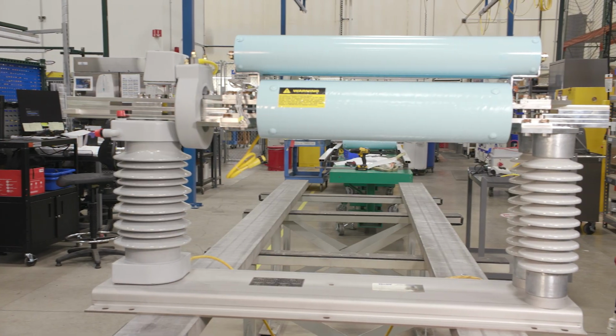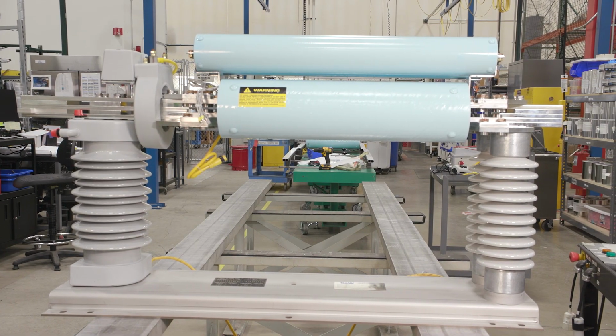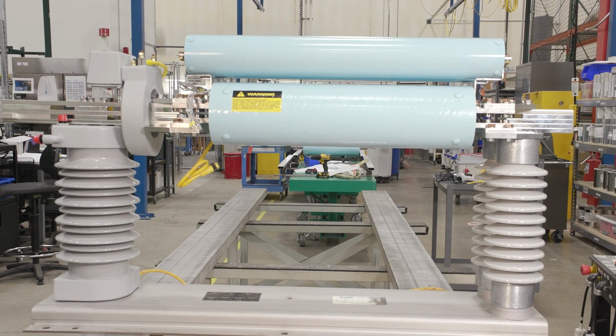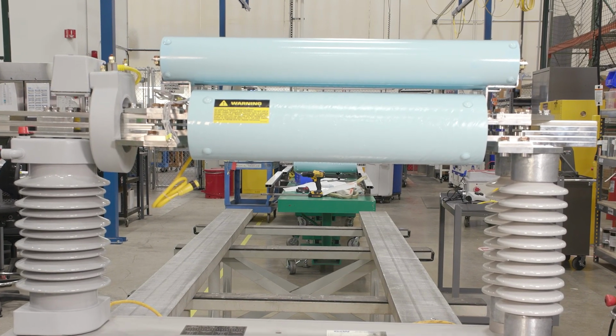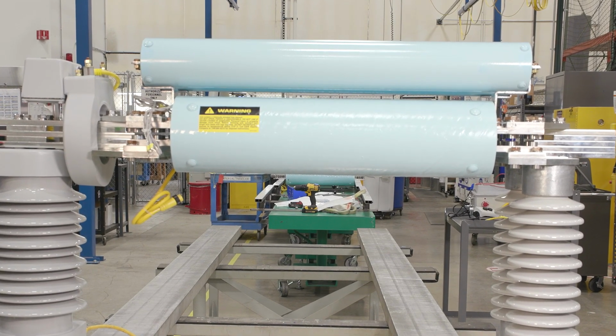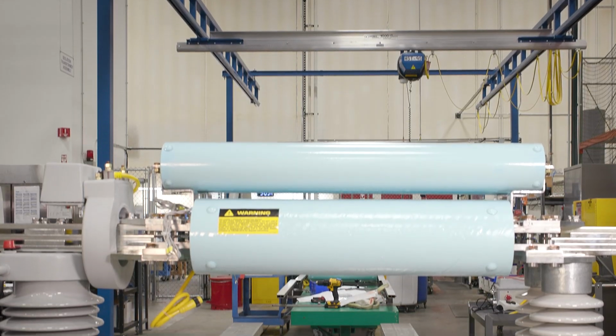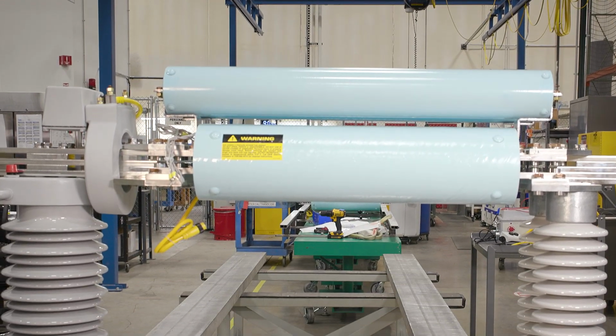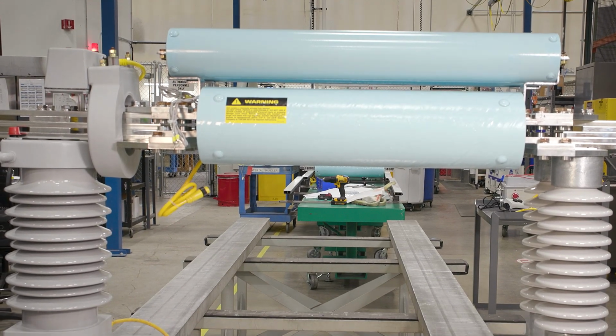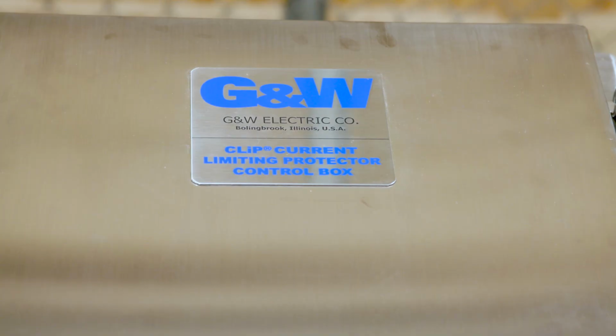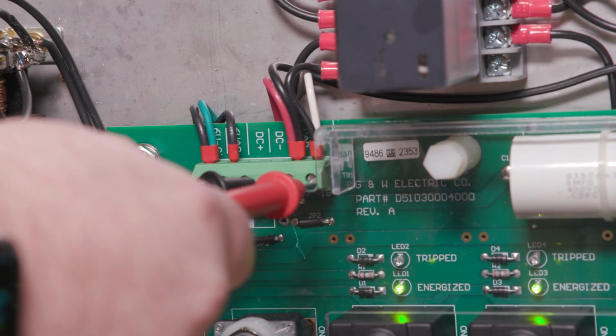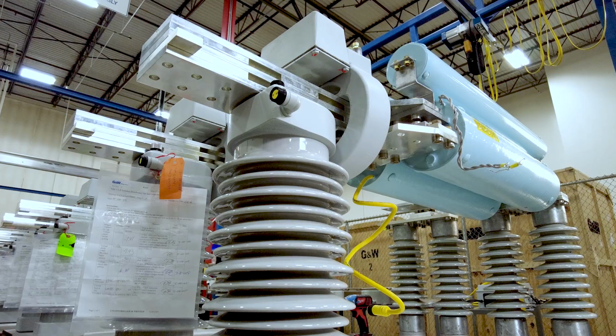The CLiP current limiting protector's unique ability to provide high continuous current capability with current limitation in under half an electrical cycle in one package makes it an economical solution for a variety of overcurrent and arc flash protection needs. In this program, we'll walk through the essential steps to safely and effectively commission the CLiP current limiting protector system.